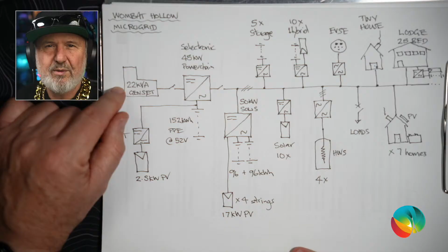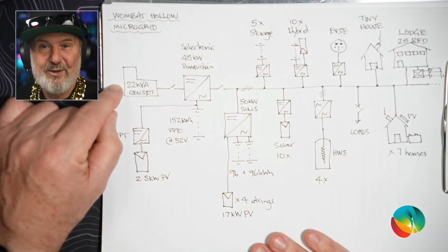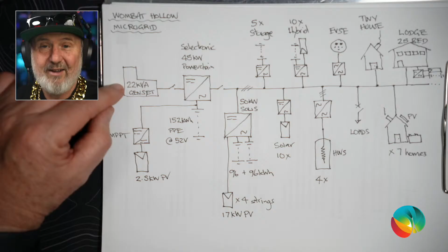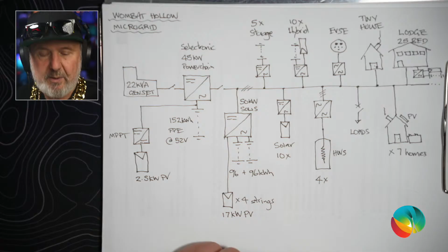You might think, well, isn't it going to use more fuel, Glenn? Actually, the efficiency goes up a little bit with larger gensets, and it might use more fuel quickly, but it generates a lot more power quickly. So you actually have a win-win. The litres per kilowatt hour is what you're worried about. The other benefit too is quiet time. Instead of this having to run for many hours, it might only run for an hour and do the same amount of energy recharge of your main grid-forming battery system.